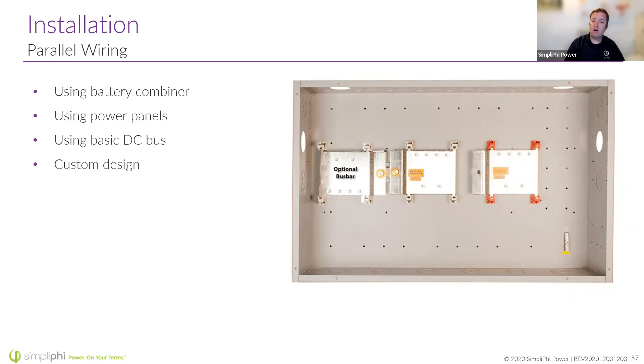You can see it here in our Boss 12 cabinets. These are our BB-3 bus bars that then go to a terminal block that then go to a combiner box. If you didn't have the second BOS 12 here, you could run directly into the Sol-Ark from that BOS 12.